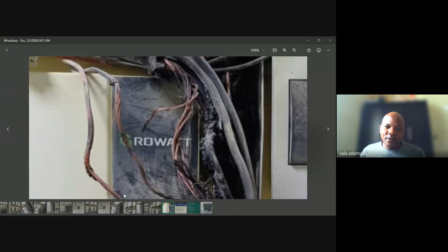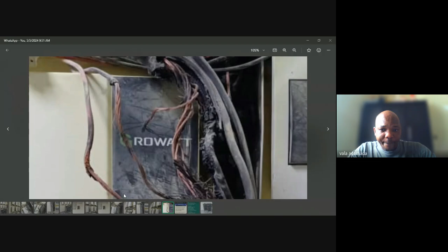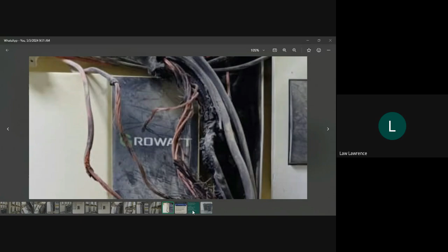Still in regards to cabling: in design, most times when you carry out calculations, you may have a particular amperage that is almost at the boundary of a particular cable you're supposed to use, close to its range limit. What advice would you give? Should one go ahead implementing that cable since it's still within its amperage range, or assume there will be further expansion later, add some tolerance, and jump to the next higher cable size? What would be your take?